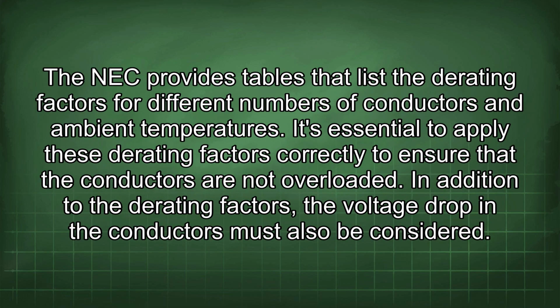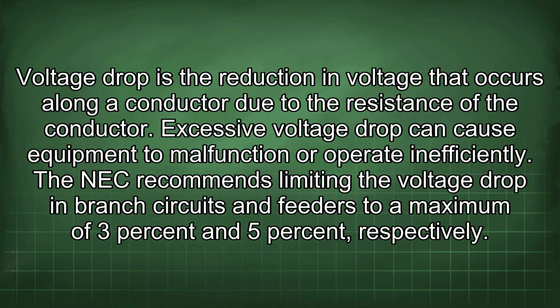The NEC provides tables that list the derating factors for different numbers of conductors and ambient temperatures. It's essential to apply these derating factors correctly to ensure that the conductors are not overloaded. In addition to the derating factors, the voltage drop in the conductors must also be considered. Voltage drop is the reduction in voltage that occurs along a conductor due to the resistance of the conductor.